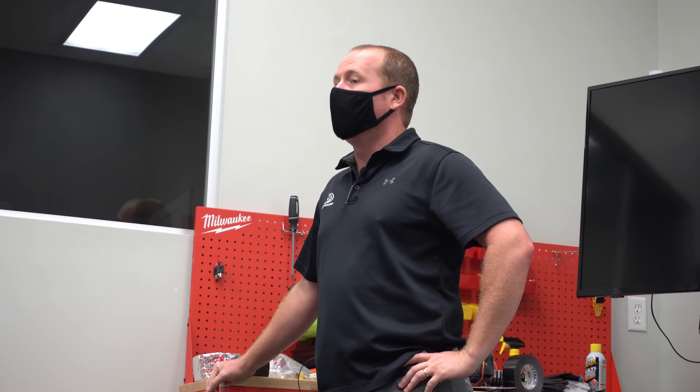Assess it. You don't necessarily want to wet certain types of soil initially — see if you can just peel it off before you wet it. But if it's the standard gunk you get in an evaporator coil, using a cleaner, hitting it on both sides, using a shop vac, using a soft bristle brush, and working top to bottom — those are usually your best bets at getting it clean.